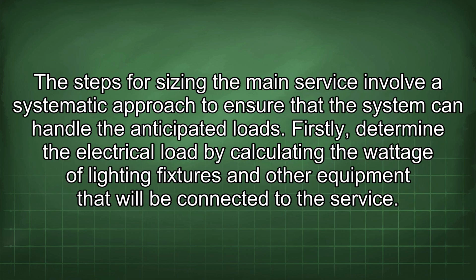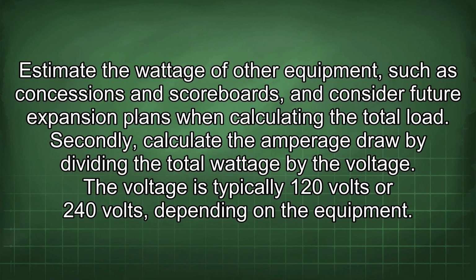The steps for sizing the main service involve a systematic approach to ensure that the system can handle the anticipated loads. Firstly, determine the electrical load by calculating the wattage of lighting fixtures and other equipment that will be connected to the service. Estimate the wattage of other equipment, such as concessions and scoreboards, and consider future expansion plans when calculating the total load. Secondly, calculate the amperage draw by dividing the total wattage by the voltage. The voltage is typically 120 volts or 240 volts, depending on the equipment.